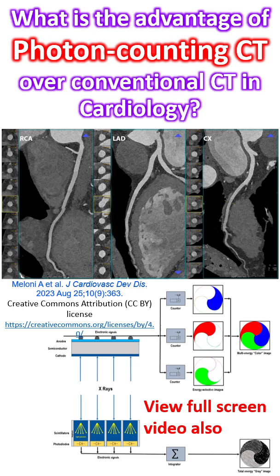The semiconductor layer is made of cadmium telluride, cadmium zinc telluride, or silicon, and has a large area cathode on the upper side. The lower side has pixelated anode electrodes. A high voltage in the range of 800 to 1000 volts is applied between the cathode and anodes to create a strong electric field.